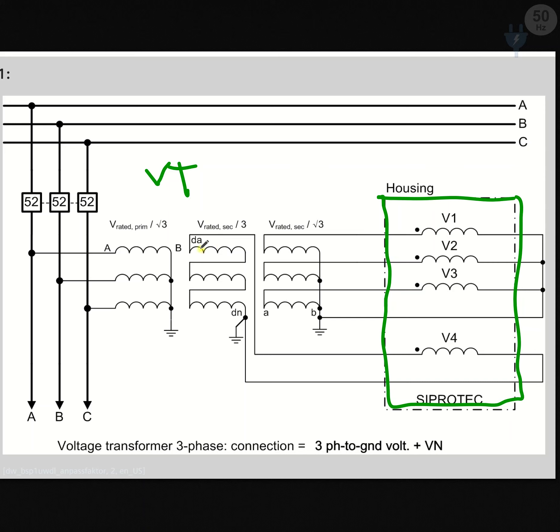In this type we have considered an open delta winding — note: the correct term is broken delta winding transformer. This is a delta winding with two open points connected to the VN input of the relay. The voltage which appears across the open delta winding here is called VN — the neutral winding voltage.